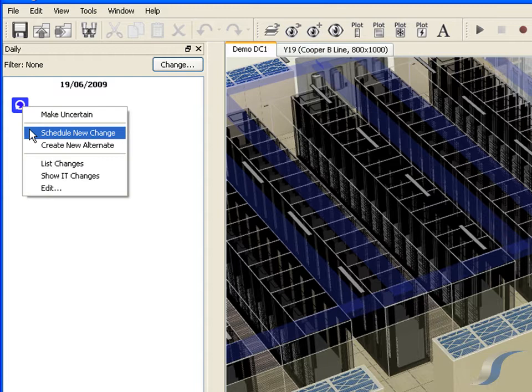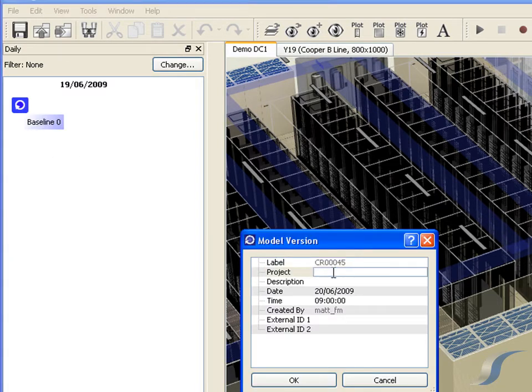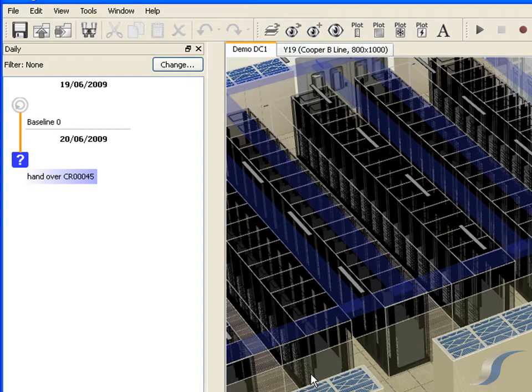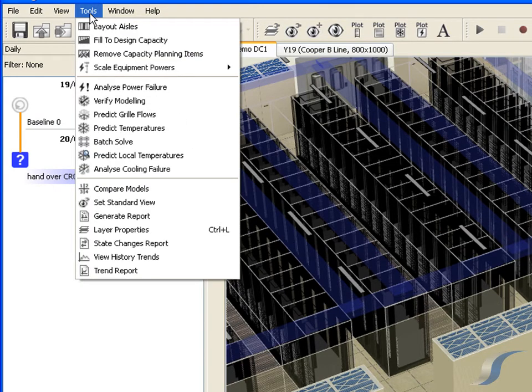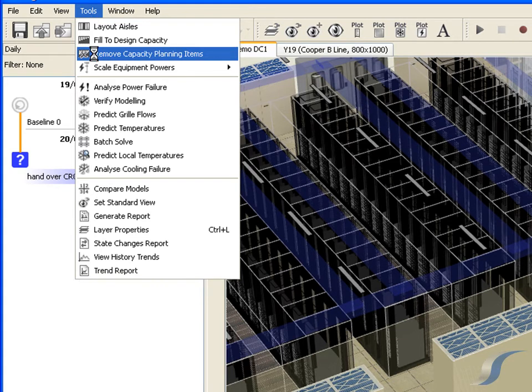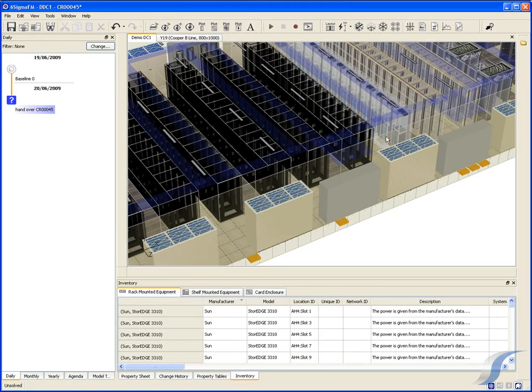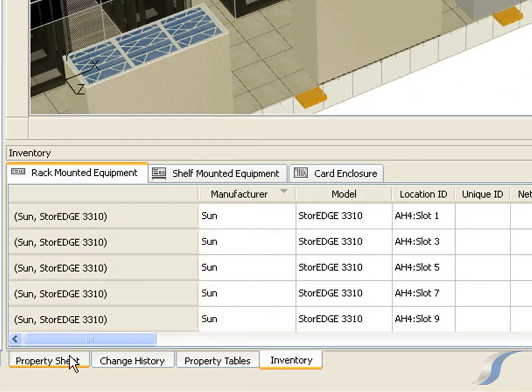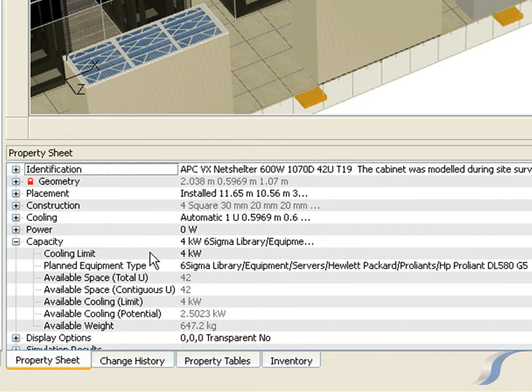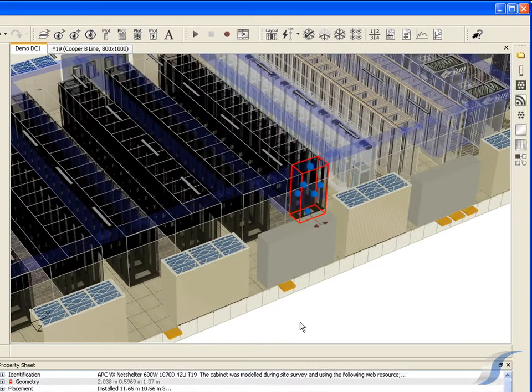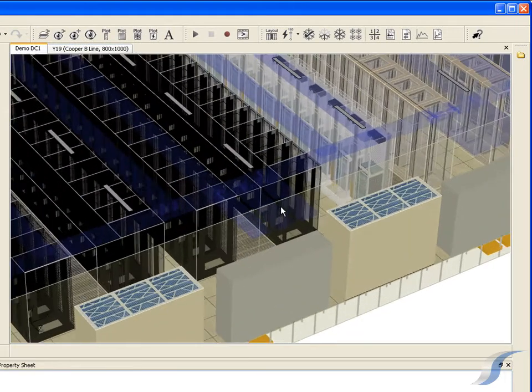We'll schedule a change with today's date and call the project 'Handover'. We can see that the cabinets are all full. However, we must remove the capacity planning items, as these are not real items but are just used to simulate the data hall at full load. Note that each cabinet has a cooling limit set in its capacity section — this is set in the design process using Six Sigma Room. The server and storage cabinets are now empty.